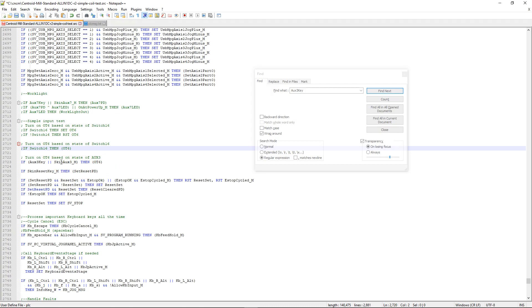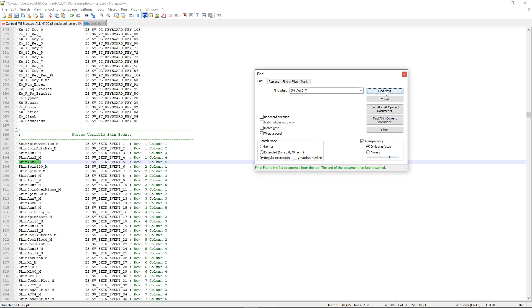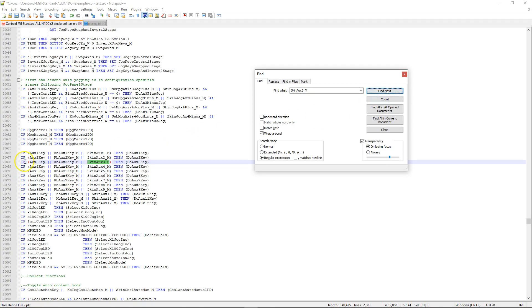Because this is the only condition controlling OT6, and I'm working from an existing program that already has logic defined, I need to check what other things are being set to that output. I can see one condition defining it as a skin event, and another where if AUX3 key is pressed, a keyboard shortcut, or the skin event occurs, it sets do_aux3. The do_aux3 is a system variable the PLC sends to the CNC software — if AUX3 is pressed, it tells the CNC software to do what it needs to do for AUX3.